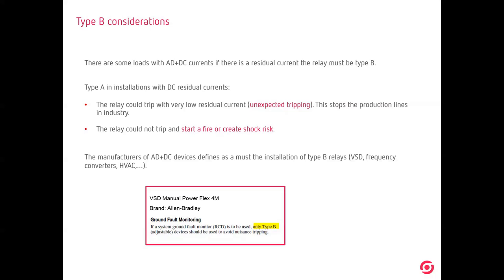create a fire. And just for finishing, the manufacturers of AC/DC devices like variable speed drives are telling that if you protect the device, you should use a type B relay. Variable speed drives, frequency converters, etc. This is, for example, a variable speed drive from Allen Bradley. This is the manual. If you open the manual, you will see that if you want to protect this device, you should use type B protection.